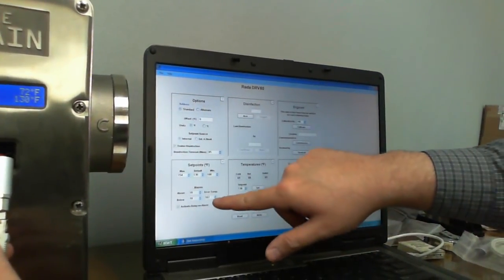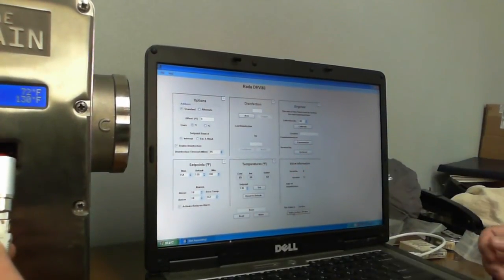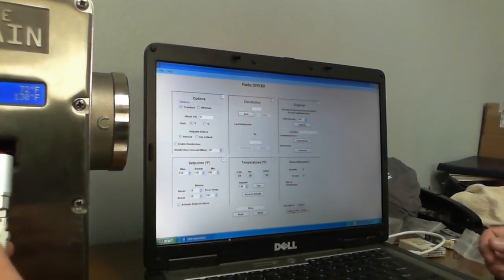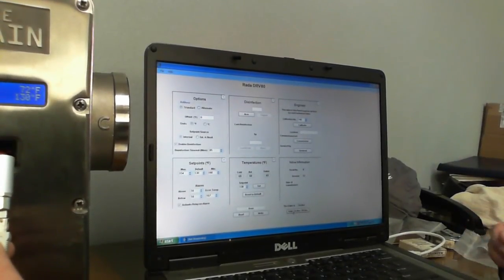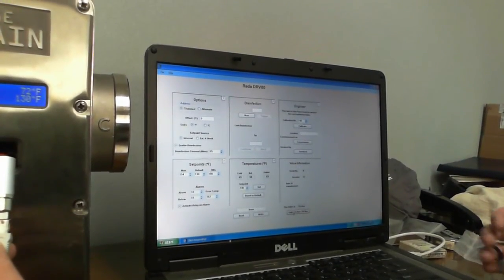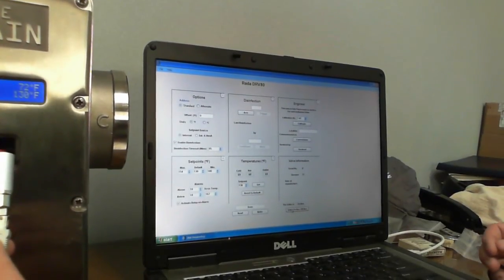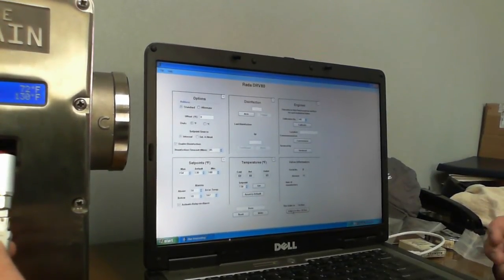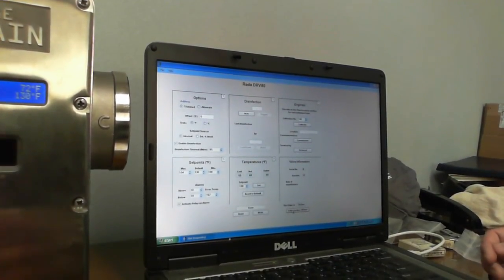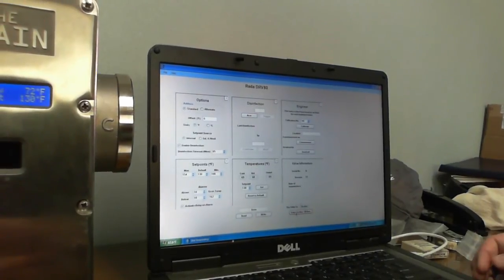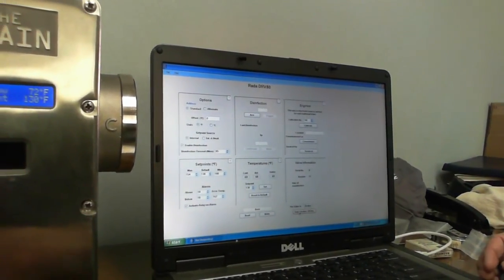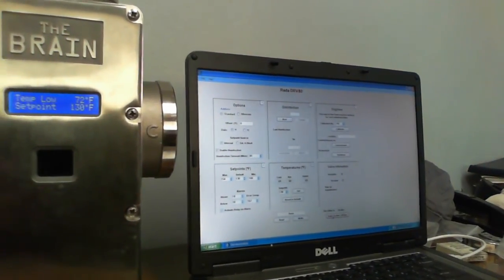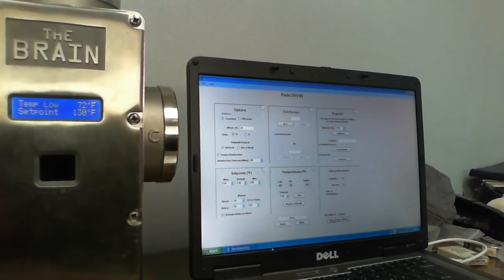Another change you might make is your high temperature. This is the maximum temperature you're going to let the valve see in degrees Fahrenheit. So if you have it at 167, if the temperature manages to go up to 167 Fahrenheit, the valve will shut off automatically and go to full cold. So those would be the common changes you might make on your DRV80 Generation 1 Armstrong mixing valve.